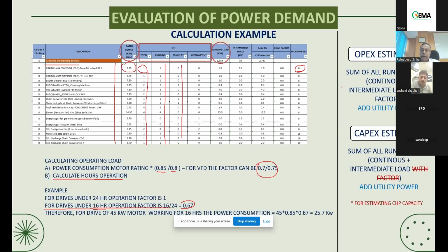Fine. Now, after that, there is an Opex estimate and a Capex estimate. What is the Opex estimate? It is the predicted power which you are going to consume. In that case, we sum up all the running loads which are continuous and all the intermittent loads, where I put a factor like 0.67 based on the running hours of the particular drive. If it is 8 hours, it is 8 by 24; if it is 16 hours, it is 16 by 24. That much diversity I have to add, and obviously some utility power, which is whatever we consume for the power plant itself. With all these we can calculate how much power you are going to consume for that particular ethanol plant, and that is going to be an operation expense.